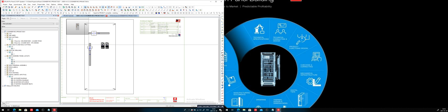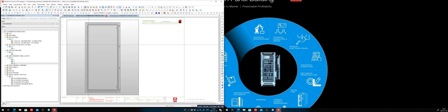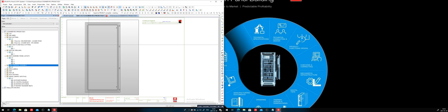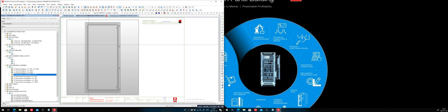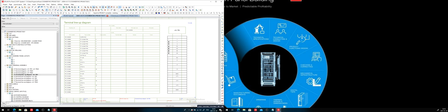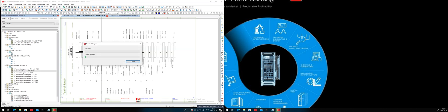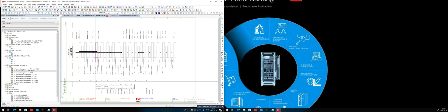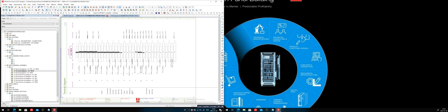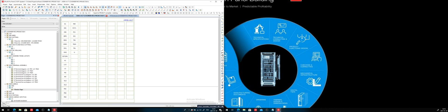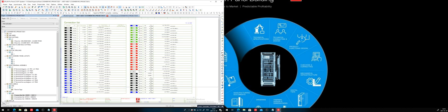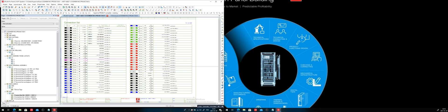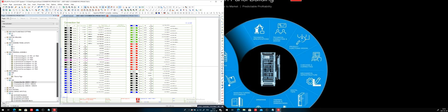Another thing that is also interesting is that ePlan looks at all the terminals not only from a construction perspective but also from a wiring perspective. What is actually connected? Jumpers, wires, everything is there. We can generate labels like device tag labels or even help you in the prefabrication of the wires. Here are all the wires that have to be fabricated with source and target and I've routed them. So as you can see we've done a lot and this all based on the schematics and the panel layout.